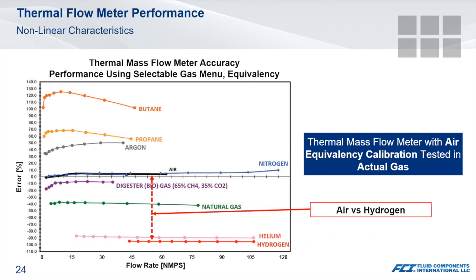This graph represents the performance of a thermal flow meter using an air equivalency under actual gas conditions. Other than 100% nitrogen, you cannot lay the curve for any of the other gases on top of the black air curve and expect linearity across the entire flow range using a simple K-factor adjustment. You also start seeing limitations on low or high flow capability depending upon the gas being measured. The best performance is achieved when you calibrate with actual gas under known process conditions.